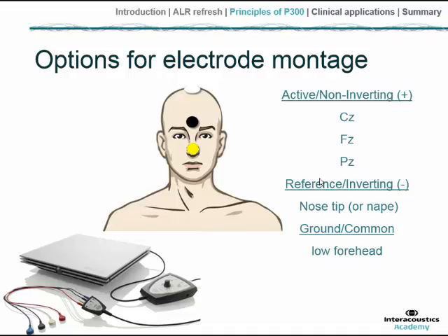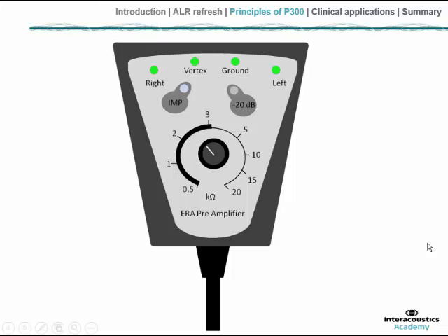From a technical point of view, we discussed possible electrode montages that might compare frontal versus parietal amplitudes. The response might be referenced to a midline such as the nose tip or nape of the neck, with a common position equidistant between the two active positions — a forehead position would be quite common. Very low impedances are always encouraged, with balanced impedance across the four electrodes; anything three kilohms or less would be ideal.